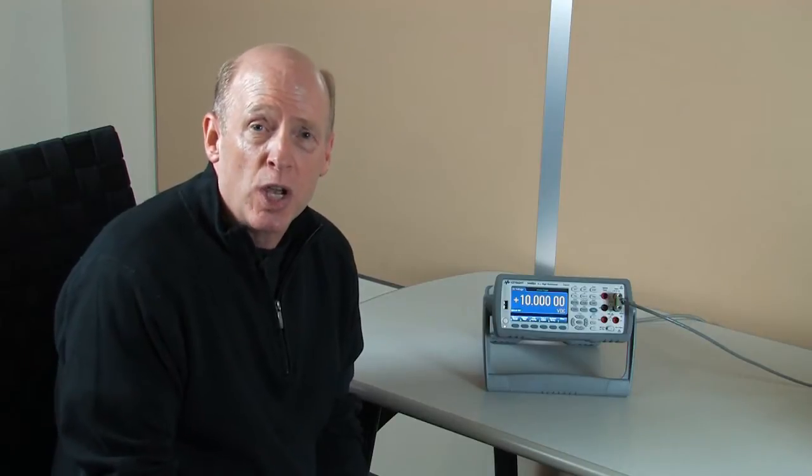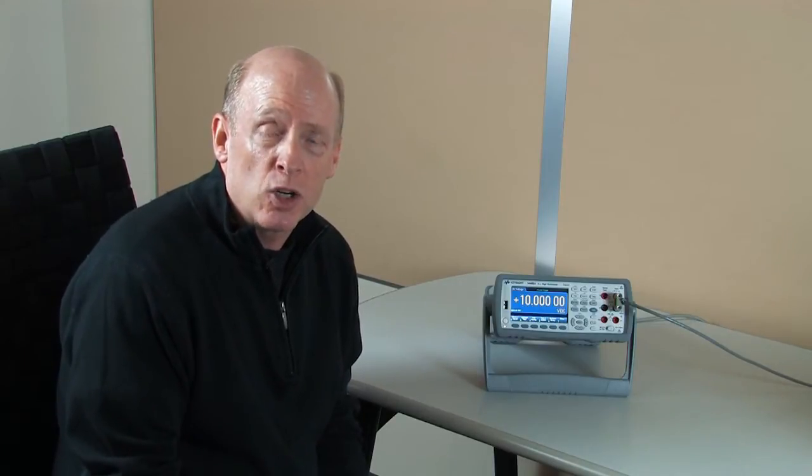Auto calibration enables the multimeter to internally compensate for accuracy and reading errors due to ambient and internal instrument temperature changes that occur over time.